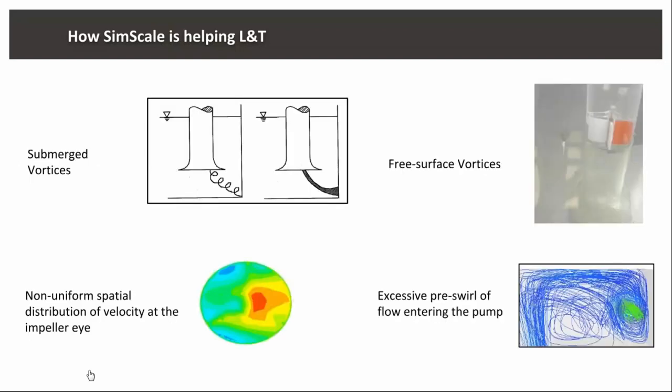Talking about today's webinar — there are certain fluid phenomena which should be avoided in sumps designed for lifting water from one place to another. The first is submerged vortices, which must be avoided and can be identified through CFD — they are represented by streamlines like a spring. The second are free surface vortices, which form while the pump is in operation and must be avoided. The third is non-uniform spatial distribution of velocity at the pump bell mouth inlet, and the fourth is excessive pre-swirl of flow entering the sump.